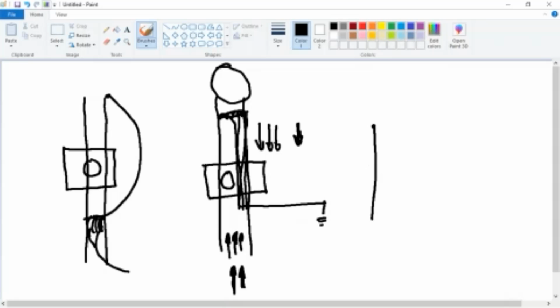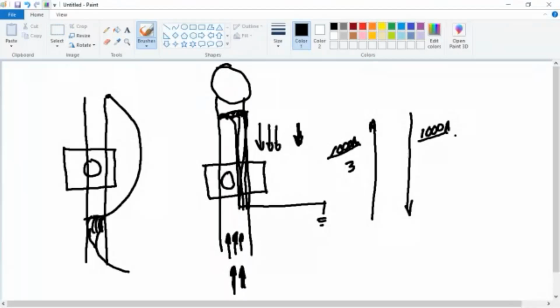So let's go over here. I'm just going to draw two arrows. Up the conductor, down the conductor. Let's go a high number for the fault current. I've got 1,000 amps going one direction, and I've got 1,000 amps going in another direction. What's going to happen with that 1,000 amps if they're going two opposite directions? Cancel out. They're going to cancel each other out. Current flow going this direction and current flow going this direction, because they're equal in a fault situation, it's just going to cancel. It's actually going to turn into zero because I've changed directions.